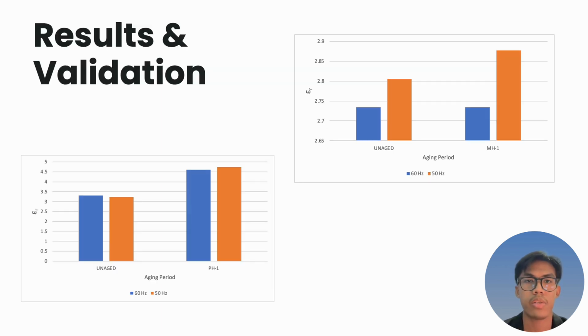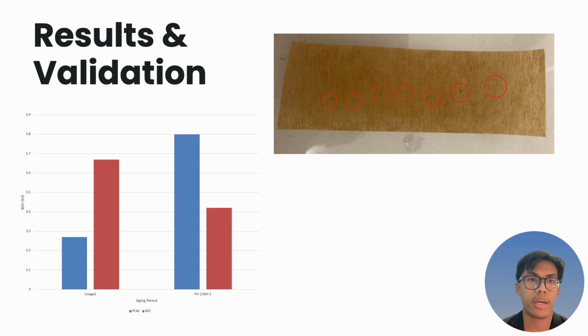So dielectric spectroscopy results show that the thermal aging caused noticeable changes in permittivity and loss tangent. As shown on the graph here, PH1 values are higher than MH1, which is mineral oil. For example, at high temperature, PH1 maintained better dielectric than MH1, which became burnt and brittle after just 2 days.